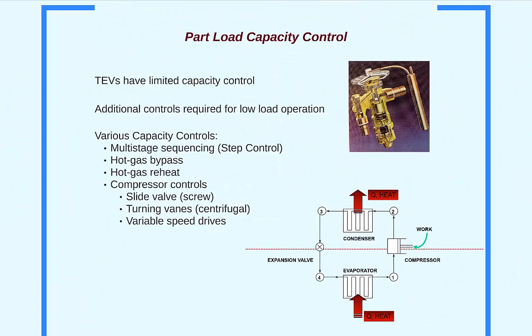The part load capacity controls we will discuss are multi-stage sequencing, hot gas bypass, hot gas reheat, as well as internal compressor controls such as slide valves used in screw compressors, turning vanes used in centrifugal compressors, and variable speed drives. You can think of all these part load capacity controls as optional add-ons that cost more but provide higher efficiencies at part load.